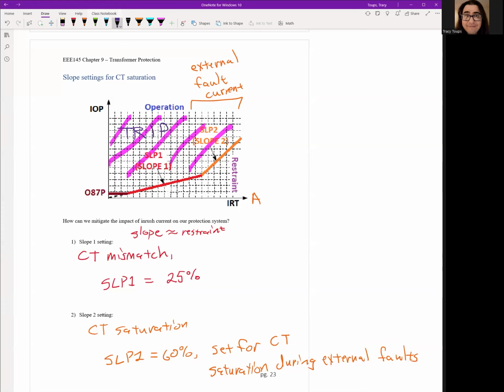Okay. Anytime we're at the bottom half, this is a blocking region. We don't want to trip. We want to restrain. Okay. So big faults typically go at the top of the page above the slope. So you're going to fault anyway. You're going to trip anyway. If it's below, you're going to block.